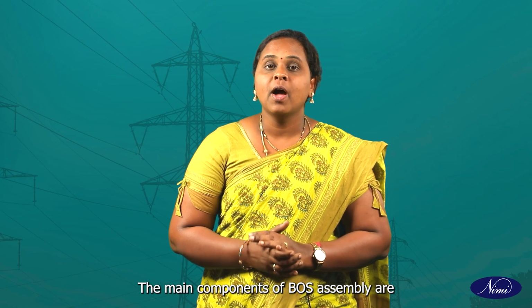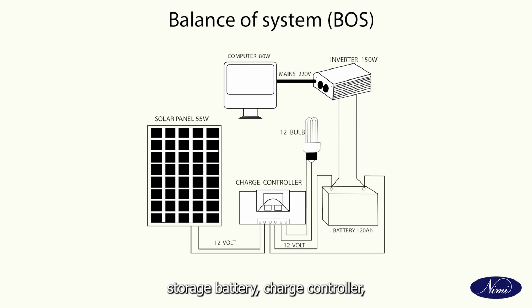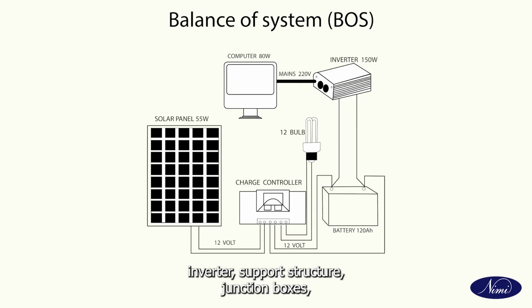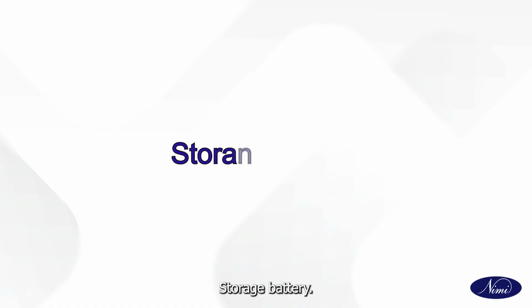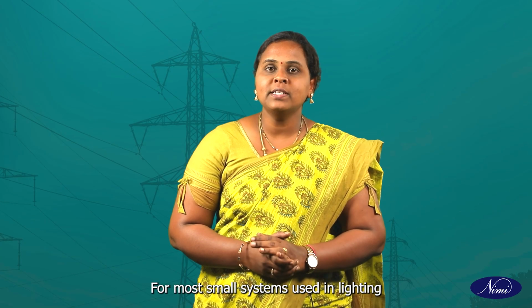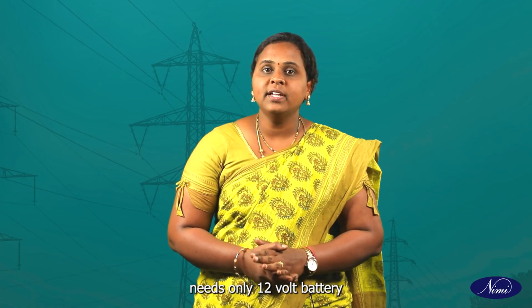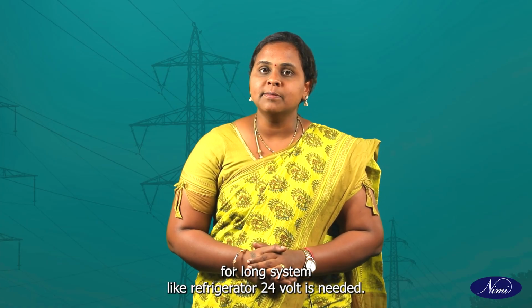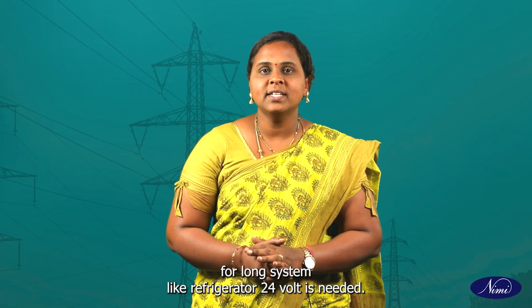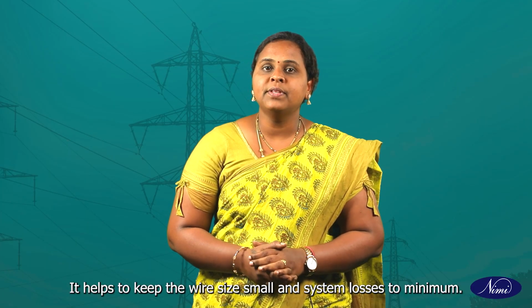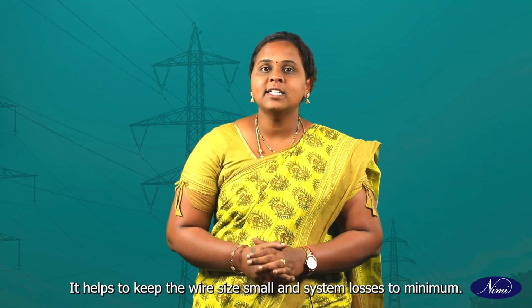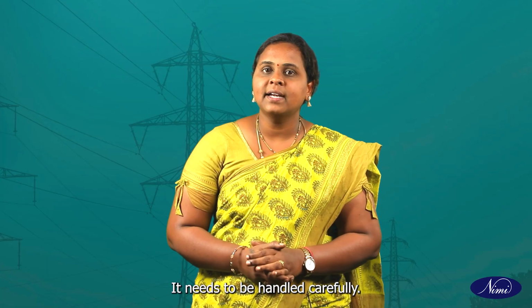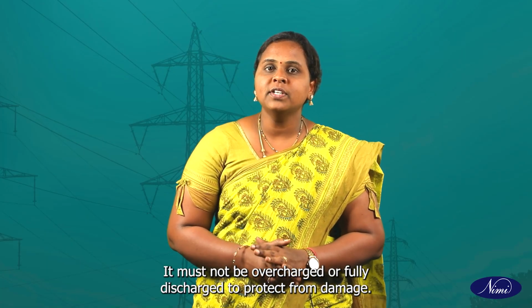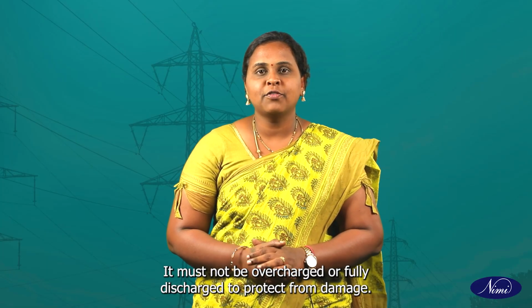The main components of BOS assembly are storage battery, charge controller, inverter, support structure, junction boxes, wires, cables and fuses, connections and switches. Storage battery. For most small systems used in lighting, only a 12 volt battery is needed. For larger systems like a refrigerator, 24 volt is needed. It helps to keep the wire size small and system losses to a minimum. It needs to be handled carefully. It must not be overcharged or fully discharged, to protect it from damage.